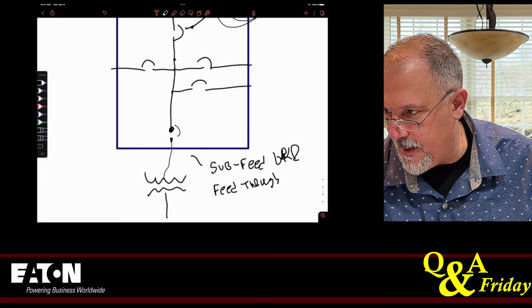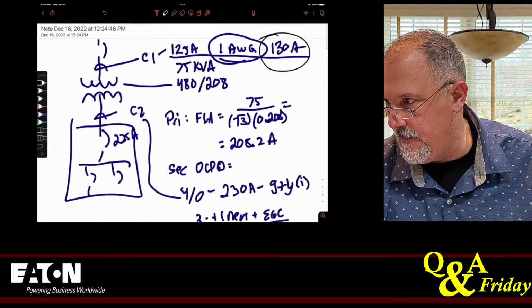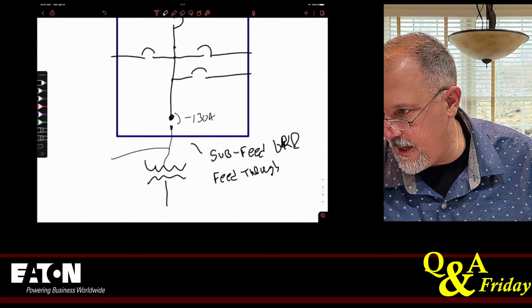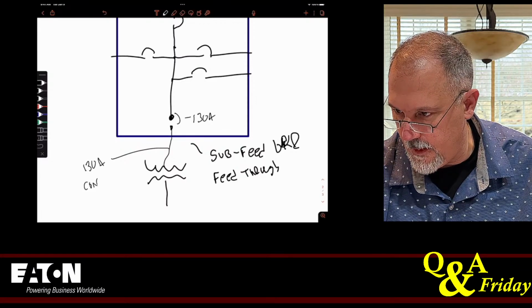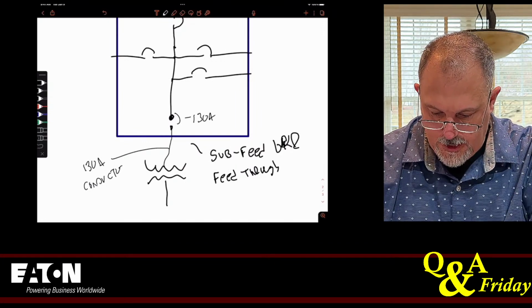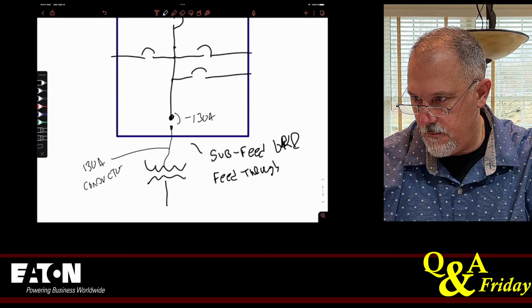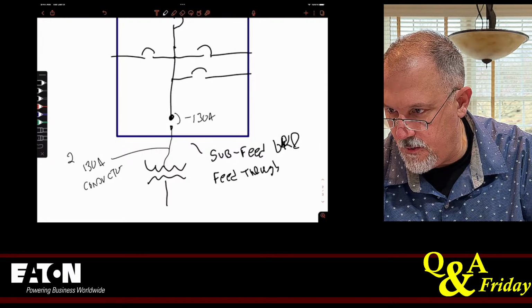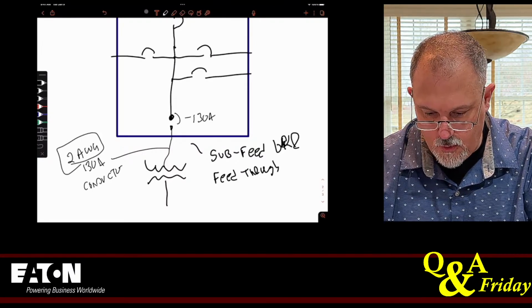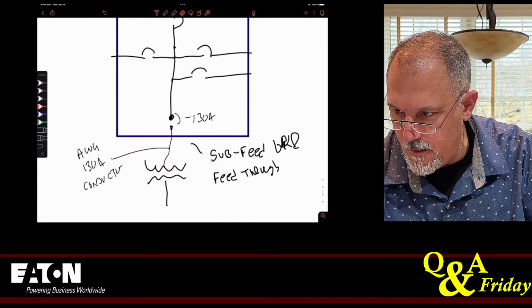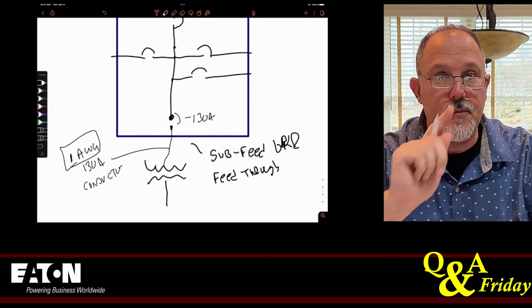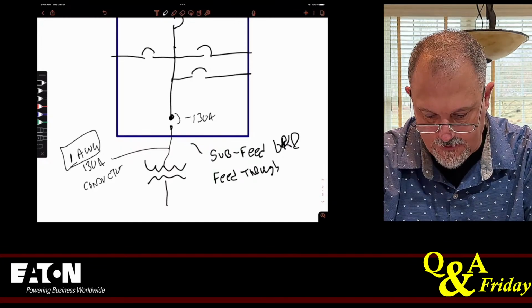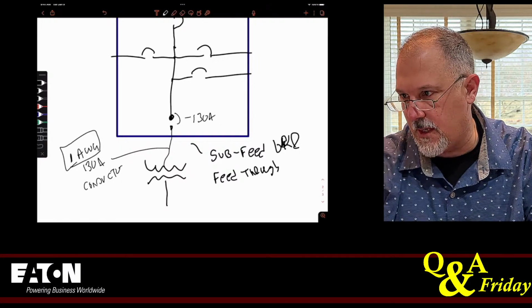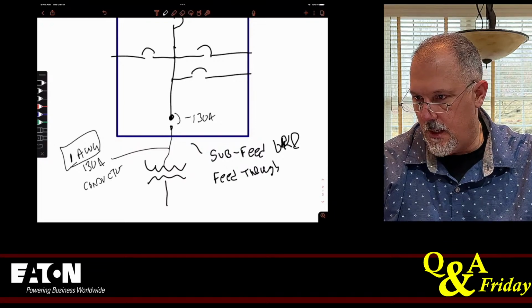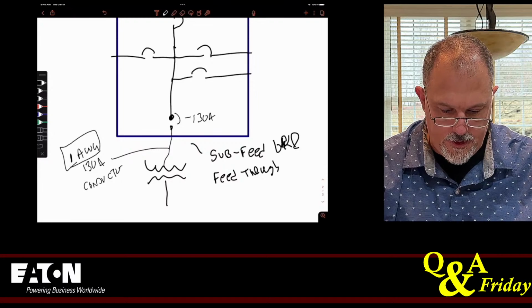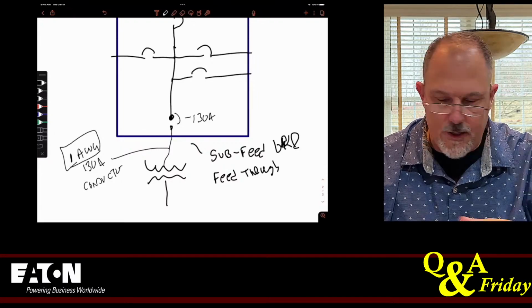So if I have a breaker here and a conductor there, and we said that was 130 amps, 130 amps worth of conductor, which we said could be a number 2. Yeah, a 2 AWG. We'll get you 100. No, that's 90 degrees C. A 1 AWG. See, it helps to read the right column, or the center column, for 75 degrees C. So a 1 gauge will get you 130 amps worth of conductor. Put that on a 130 amp breaker. But I can't get a 130 amp breaker, so I can do 150 amp.